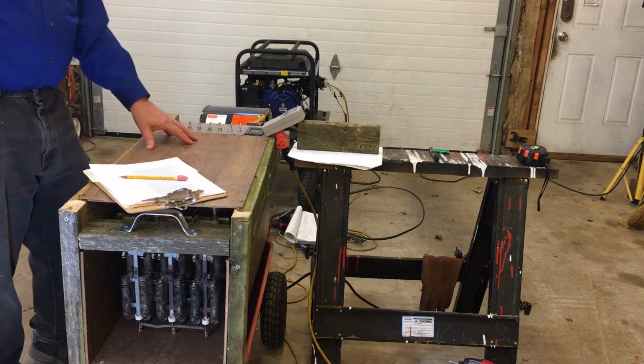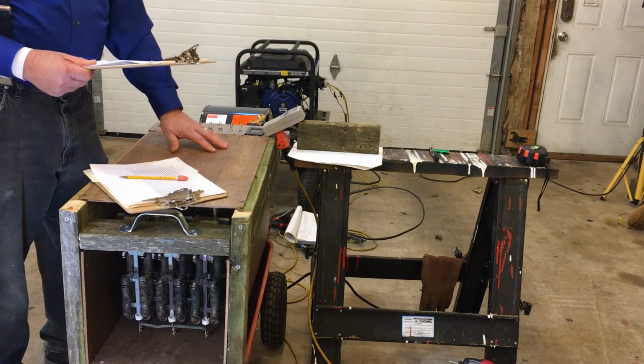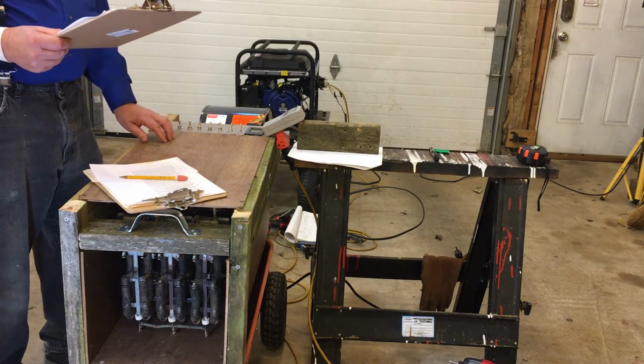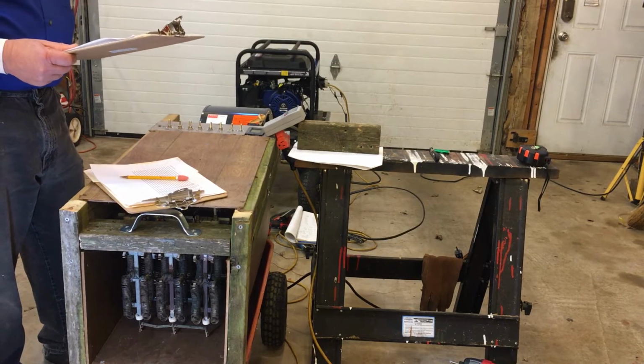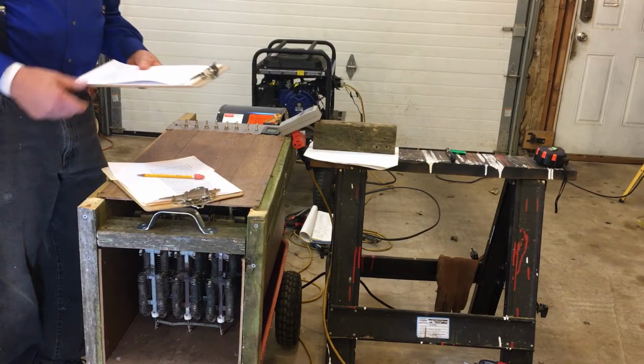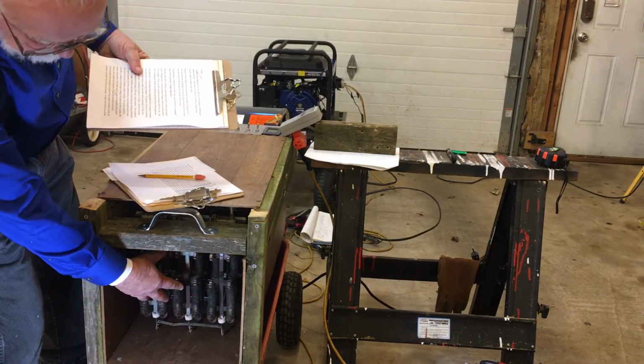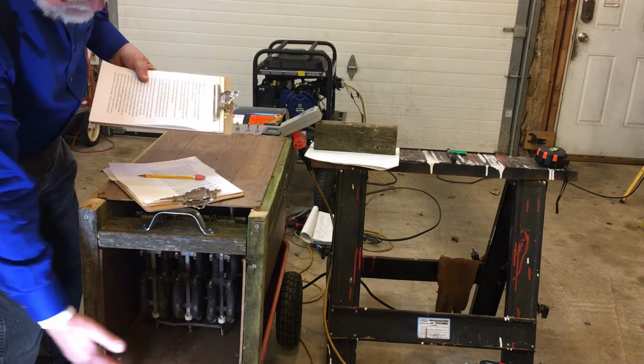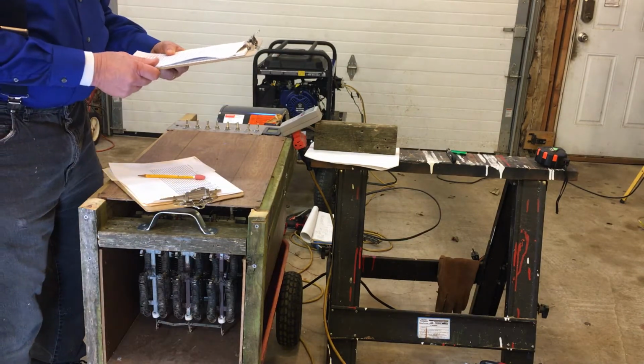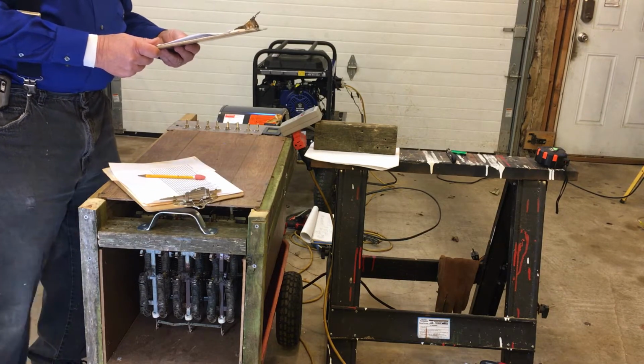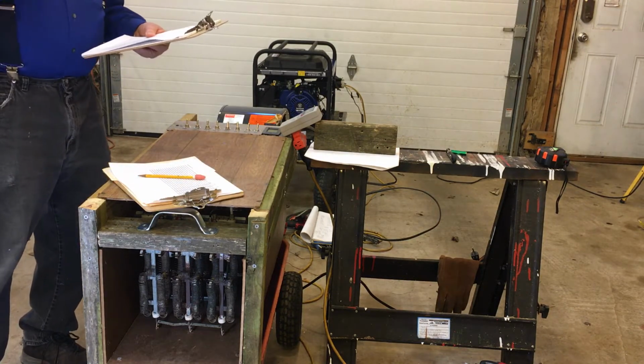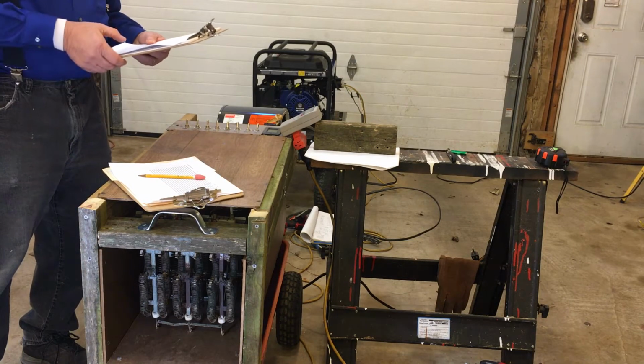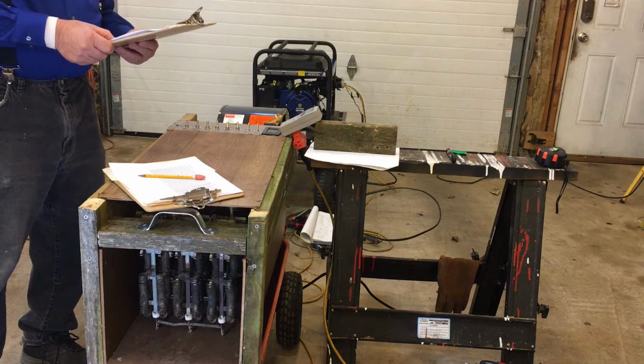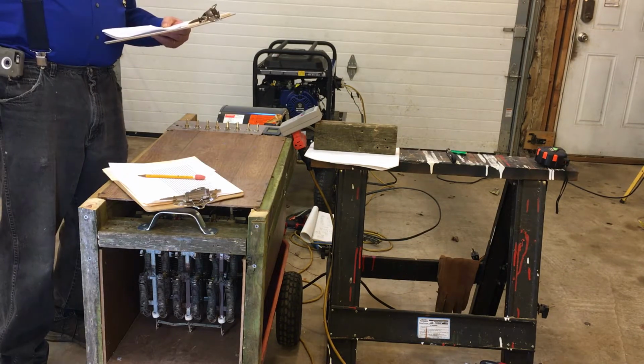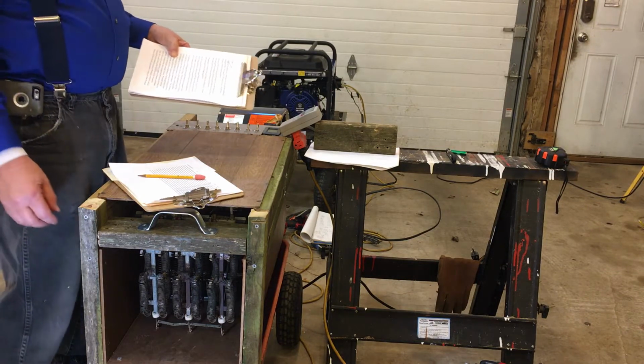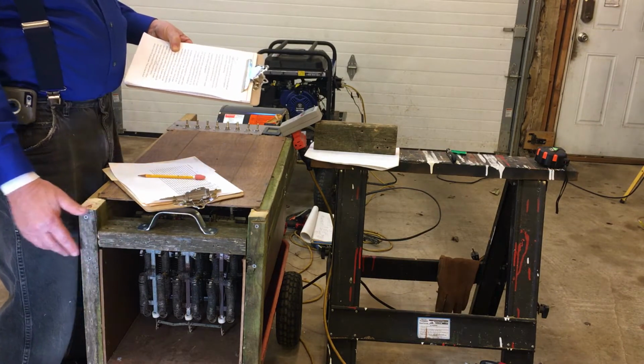This is my homemade load bank. As you can tell, it's been assembled from salvage material that came out of my son's shop. The device contains 9 heating elements which are suspended in this tube, which is about a foot square, give or take. And each of these heating elements is rated for just under 5 kW when operated at 240 volts. Of course, today we'll be operating only at 120 volts on these elements. Each heating element has a resistance of approximately 11.5 ohms.